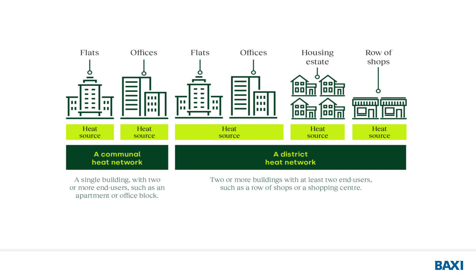Now, obviously the heat network is a big thing at the present time. So there are two types. There's the communal network system, which relates to just a single building, so you have your plant room either in the building or outside. That would then be feeding a distribution system into HIUs for each apartment, or offices, or whatever it might be. So that's the kind of communal system. The big one, the heat networks, is where you've got a centralised plant room feeding several sites off a district heating main effectively.